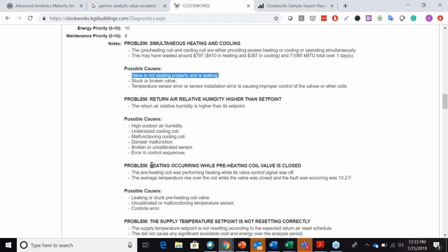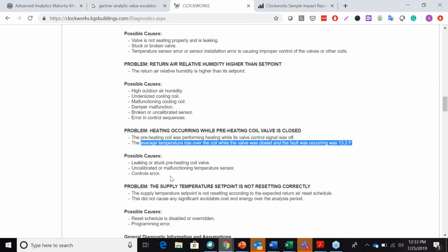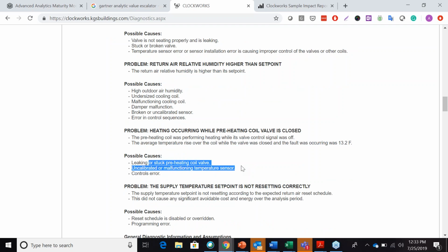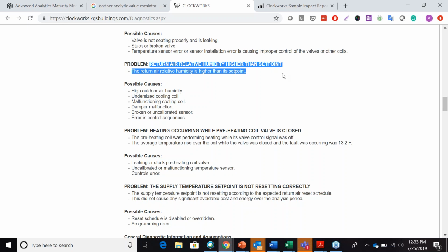In fact, I can see that is the root cause because it's listed here as well. How do we know that the heating valve looks like it's leaking? Well, it says that the average temperature rise over the coil while the valve was closed and the fault was occurring was 13.2 degrees. So where is that temperature gain coming from across the coil if there's no hot water going through it? And the possible cause here, direct resolution, either the valve is leaking or stuck, could be an uncalibrated or malfunctioning temperature sensor, or a controls error. Either way, worth investigating. And I jumped ahead of the return relative humidity issue here. It might be causing comfort issues, for certainly a range of possible mechanical problems here that could be leading to that.